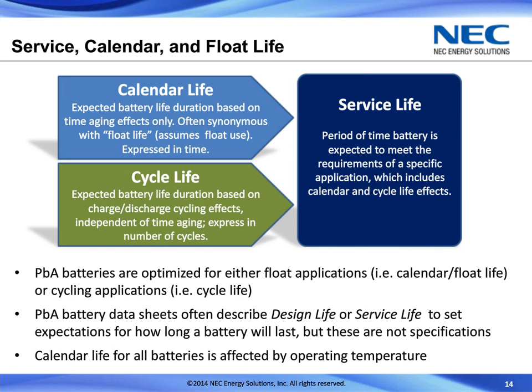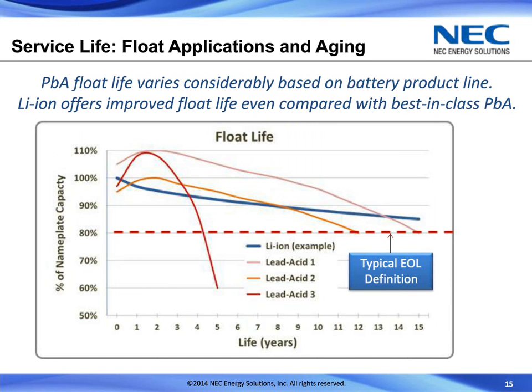So if we look at service life and compare lithium-ion versus various lead-acid, we really have to look at it and say, gee, the float life and the aging of the battery varies considerably based on what the battery product line might be. Some actually have relatively short lifespans, as illustrated in this chart. It can be as short as 4 or 5 years before their capacity degrades to, say, an 80% level, basically meaning the capacity of the battery is 80% of what its original nameplate capacity was. And you can see that it can be pretty good for a while and then kind of falls off a cliff after time. Or it might more slowly degrade.